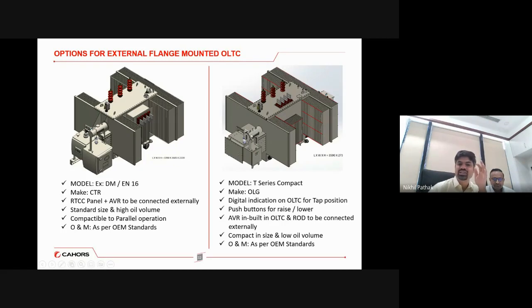This OLTC has an inbuilt AVR. Secondly, the oil content is also low because the size has been optimized. For example, in 33 kV, I think 500 to 600 liters of oil is there. 700 liters in the 33 kV model of OLTC CTR1, and in the 33 kV OLG model it is hardly 150 liters, less than 150 liters. So there are differences between the two.